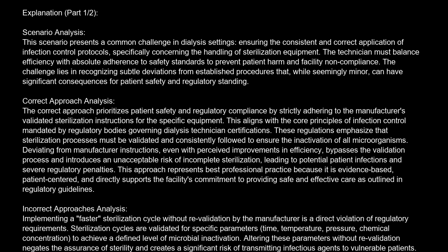Incorrect approaches analysis. Implementing a faster sterilization cycle without revalidation by the manufacturer is a direct violation of regulatory requirements. Sterilization cycles are validated for specific parameters: time, temperature, pressure, chemical concentration, to achieve a defined level of microbial inactivation. Altering these parameters without revalidation negates the assurance of sterility and creates a significant risk of transmitting infectious agents to vulnerable patients. This constitutes a serious regulatory failure and an ethical breach of the duty of care.